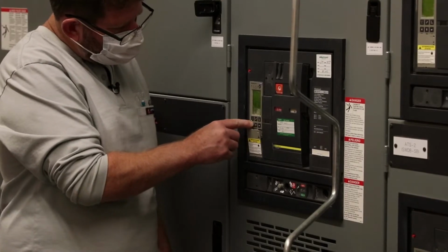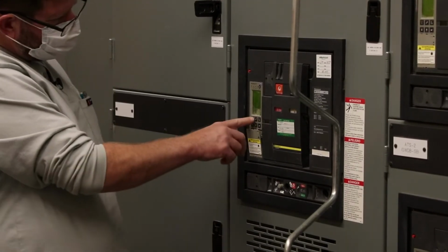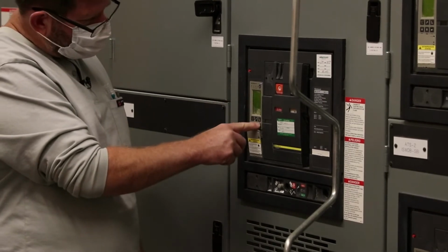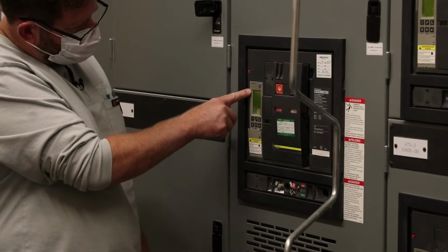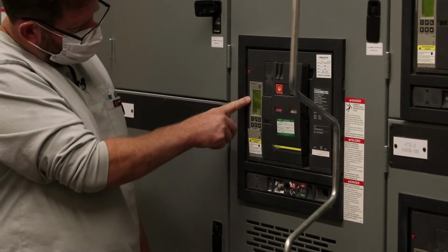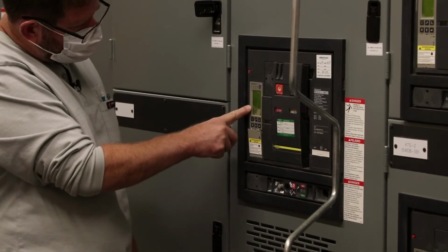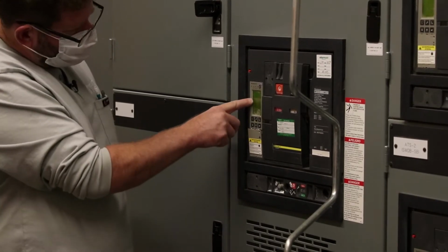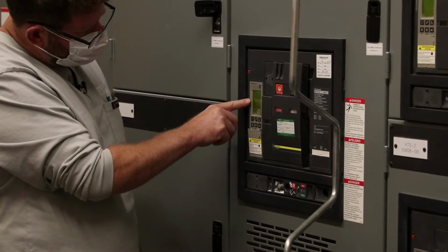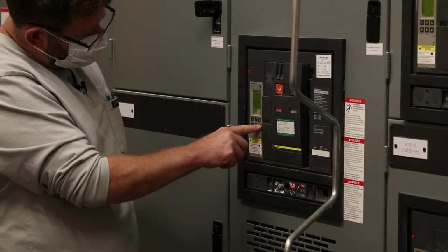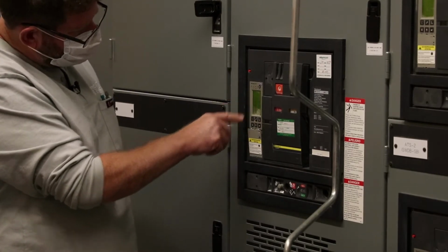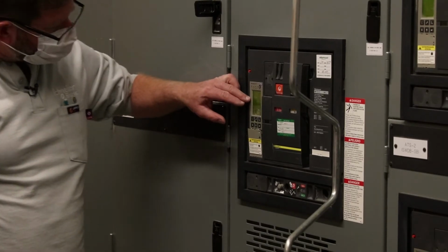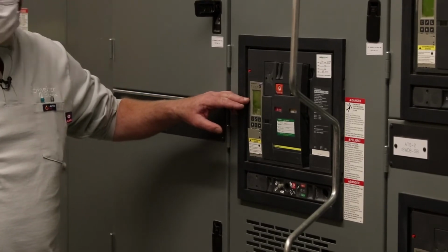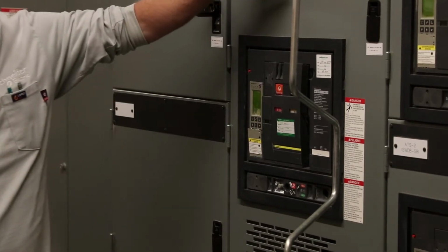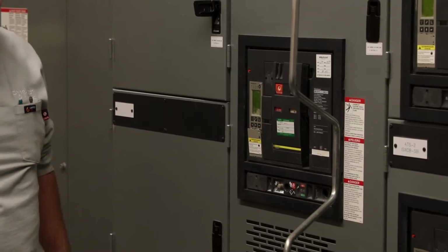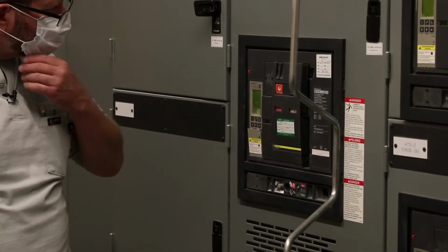Other function you have here on the trip unit, you have the wrench, that's maintenance. You have history logs. If the breaker trips, you can come into the history log and go to trip history, and it'll tell you with a date time stamp all the times it's tripped. Showing here that you had a ground fault trip on April 30th of this year. If you want to know more information about it, you push the enter button, and it's going to give you again the date time stamp and what the current was. This likely was during testing. Yeah, testing was done April 30th. The ground fault trip happened on April 30th. It was just for testing.